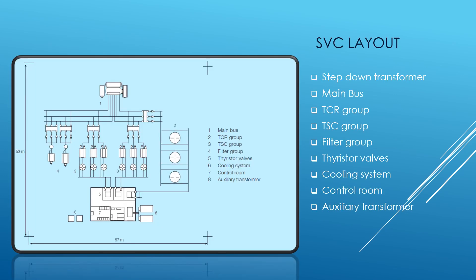Now let's look at the SVC layout. The layout on the screen is an ABB 500 MVAr SVC connected to the 132 kV controlled bus to stabilize the voltage during various network conditions, including major disturbances such as loss of feeding. As you can see, it contains a step-down transformer, thyristor-controlled reactor, thyristor-switched capacitor, filter groups, thyristor valves, cooling system, control system, and auxiliary transformer.